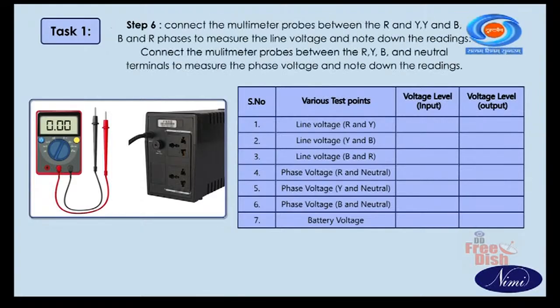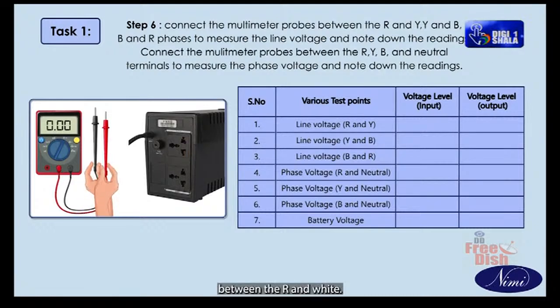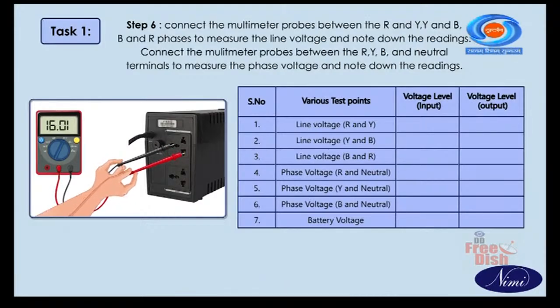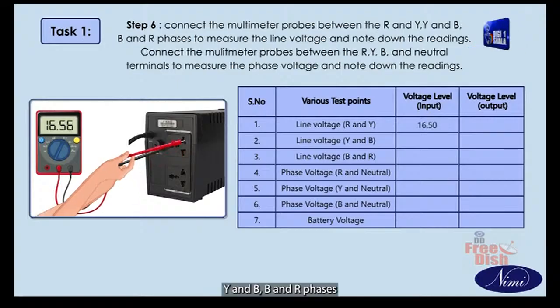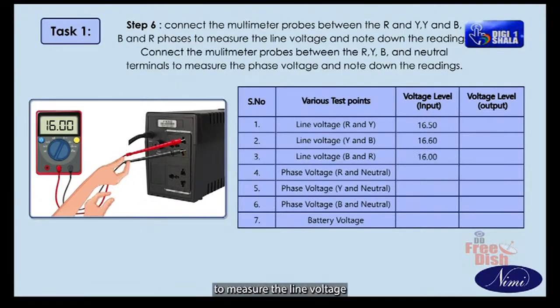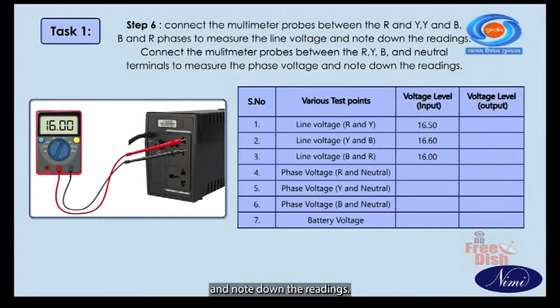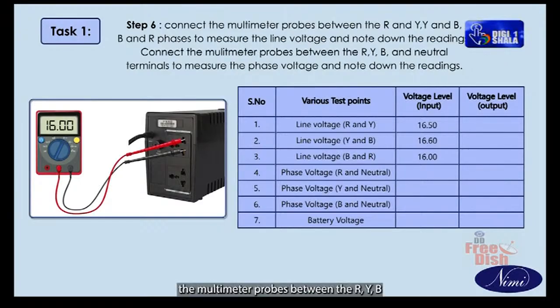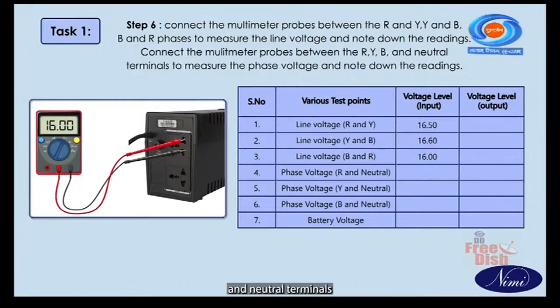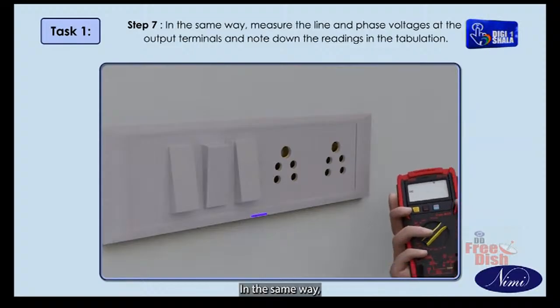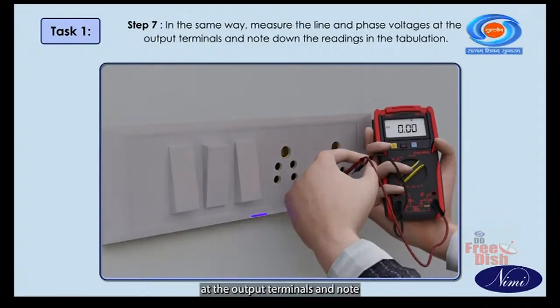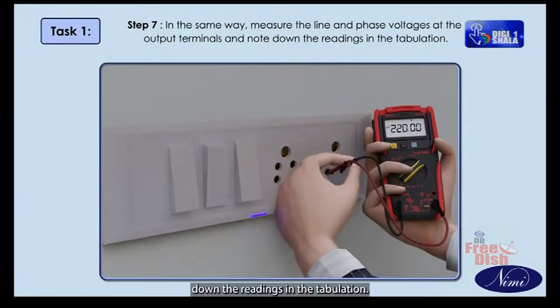Step 6. Connect the multimeter probes between the R and Y, Y and B, and B and R phases to measure the line voltage and note down the readings. Connect the multimeter probes between the R, Y, B and neutral terminals to measure the phase voltage and note down the readings. Step 7. In the same way, measure the line and phase voltages at the output terminals and note down the readings in the tabulation.